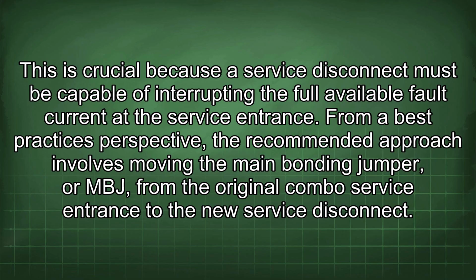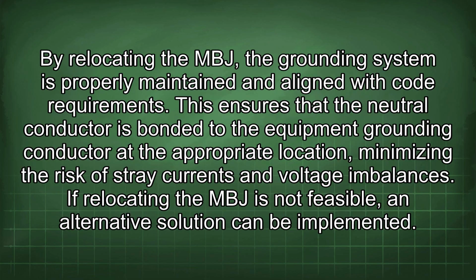From a best practices perspective, the recommended approach involves moving the main bonding jumper, or MBJ, from the original combo service entrance to the new service disconnect. By relocating the MBJ, the grounding system is properly maintained and aligned with code requirements. This ensures that the neutral conductor is bonded to the equipment grounding conductor at the appropriate location, minimizing the risk of stray currents and voltage imbalances.